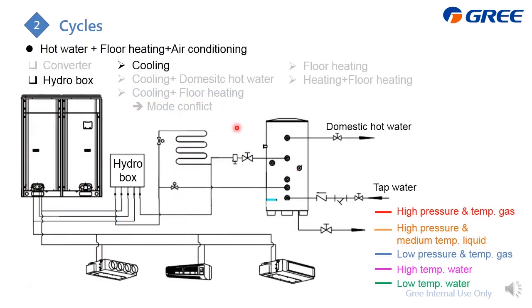As for the hydro box, it can also produce the domestic hot water. And for this type, it can connect with the floor coil and also the water tank. Of course, this one is the inner coil. In this example, this is the outdoor unit, hydro box, floor coil, water tank, and also 3 indoor units. So first is the cooling. Here is how the refrigerant flows, also from the outdoor unit directly. For example, these two require cooling. Then the refrigerant will be sent from the outdoor unit to the indoor unit and get expanded and become low temperature. Then it can absorb heat, become gas and flow back to the outdoor unit. So the outdoor unit releases heat, and the indoor unit absorbs heat.